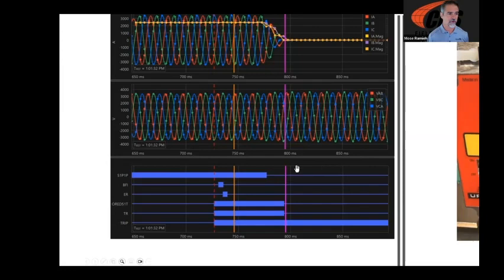And to note that, right, here's the initiation of the trip signal right here, this red dotted line. That's the initiation of the trip signal. That's when the relay finally timed out and says trip the breaker. And then we can see this purple line, how long it took the breaker to trip from command to trip to actually opening and de-energizing the system. And then it's just a matter of counting the cycles, right? So if I pick this green waveform here, there's 1, 2, 3, 4. So before the 5th cycle of the green phase, we are at a de-energized state. So once again, that gives me a great picture of this breaker is going to operate in 5 cycles like most systems are designed to do.